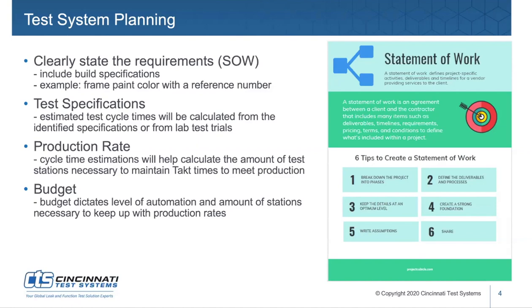Is it an IP67 spec? Well, that's easy. It's 1 meter of water. 1 meter of water equals 1.4 psi. And then leak rates, identifying either a pressure drop or the correlated volumetric flow rate of that specification, 1 SCC per minute, maybe 10 SCC per minute.